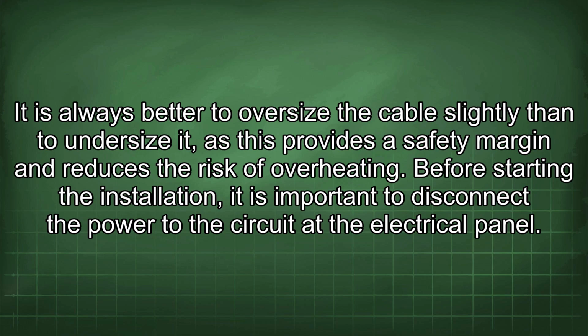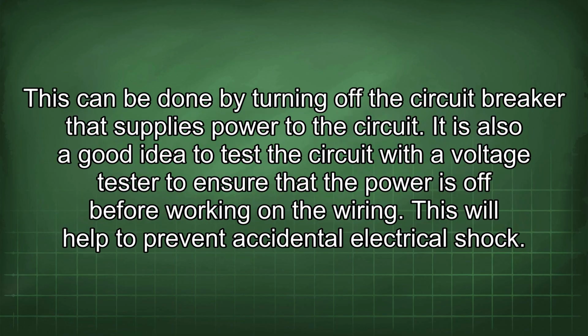Before starting the installation, it is important to disconnect the power to the circuit at the electrical panel. This can be done by turning off the circuit breaker that supplies power to the circuit. It is also a good idea to test the circuit with a voltage tester to ensure that the power is off before working on the wiring. This will help to prevent accidental electrical shock.